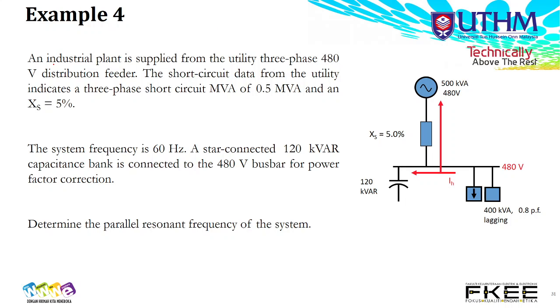Let's say we have an industrial plant supplied from the utility, 3-phase 480 volt distribution feeder, and the short circuit data from the utility indicates a 3-phase short circuit MVA equal to 0.5 MVA and XS equal to 5%. This is the per unit value of the source, which is XS equal to 0.05 per unit. The system frequency is 60 Hz. A star connected 120 kVAR capacitor bank is connected to the 480 volt bus bar for power factor correction. Determine the parallel resonance of the system.